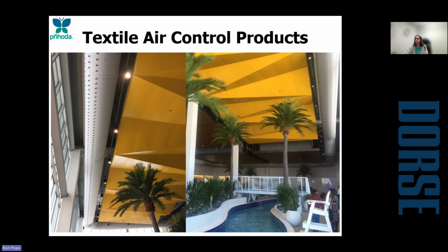So what we did is we took those textile air control products, and we turned those 90 degrees here to blow up under that clouded ceiling. And we used the Coanda effect to our advantage there. So we suctioned that air to the clouded ceiling and allowed it to fall at a natural rate to not cause any type of discomfort with the occupants in the swimming pool area, as well as to make sure that we weren't blowing air directly at the water, affecting the chlorine and all of that in the water.